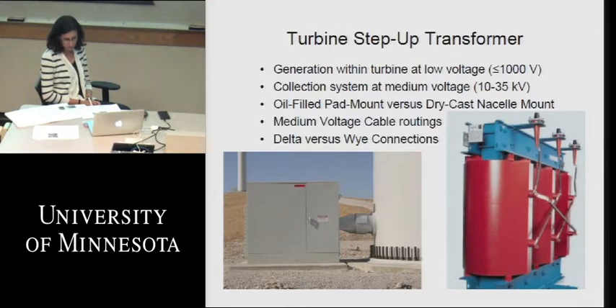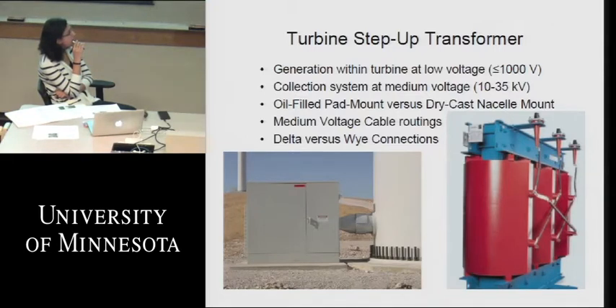Again, I talked a little bit about the pad mount versus the dry cast, and where you mount them, on the bottom of the tower versus the top of the tower. But you need to connect up to that transformer. In the picture on the left, with the oil bath transformer on the outside of the tower, there has to be some way to get those down-tower power cables into the wiring cabinet of the transformer. Either they go through the concrete of the foundation and stub up into that transformer cabinet, or we build a penetration in the tower, as you see in this picture, and build a little wireway in the field to accommodate those cables going into the wiring connection side of the transformer box, which is on the right of the transformer in that picture.